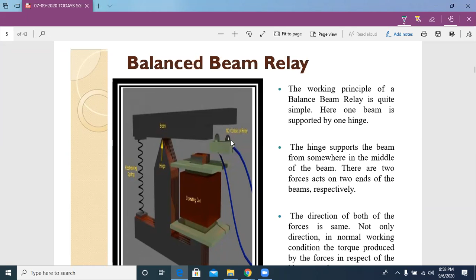When the beam is in balanced mode, the trip coil contacts are open, so there is no current in the trip coil. When a fault happens, due to that fault, the secondary of the transformer sends more current to the magnetic coil. That's why the magnetic coil produces a high amount of operating torque, and the operating torque dominates the restraining torque. Ultimately the beam moves downwards. When the beam moves downwards, trip coil contacts are closed. When the trip coil contacts are closed, circuit breaker contacts are open. So in this way we can explain the balanced beam type relay.